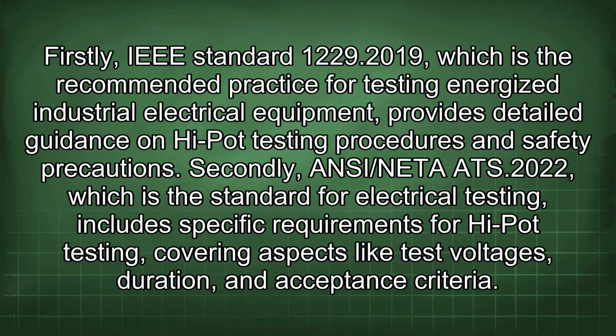Firstly, IEEE Standard 1229.2019, which is the recommended practice for testing energized industrial electrical equipment, provides detailed guidance on high pot testing procedures and safety precautions. Secondly, ANSI/NETA ATS.2022, which is the standard for electrical testing, includes specific requirements for high pot testing, covering aspects like test voltages, duration, and acceptance criteria.